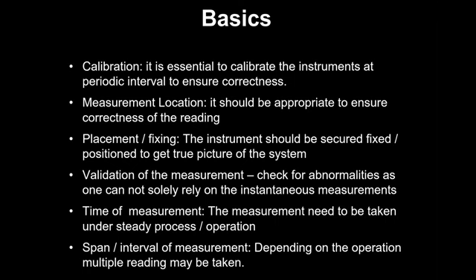Now that air goes inside and occupies the space close to your instrument, because it is going to mix with the flue gases only at some distance. Then it's not going to matter, because you have more than a lakh meter cube of gas going. A few ml or a few liters of ingress is not going to show, but at that measurement point it was showing, because that's where that air was entering from. So that was the reason why we were getting a wrong reading.